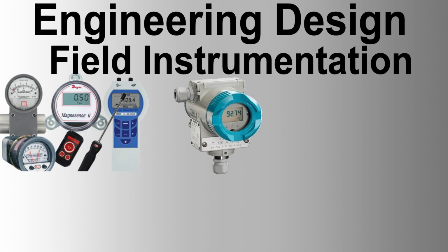Relief valves. Relief valves must be selected according to Shell DEP 80.45-1010 and designed, constructed, tested, and marked in accordance with API RP 520, API RP 521, API RP 526, and API RP 527. Valves must have metal-to-metal seats, with resilient seat seals considered for specific applications. Bottom guides are acceptable only in special circumstances.